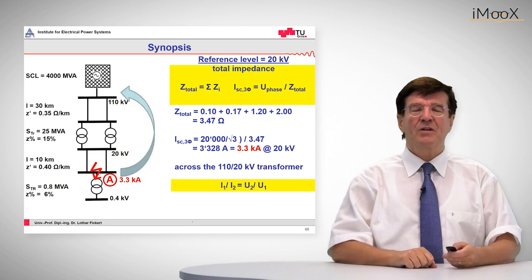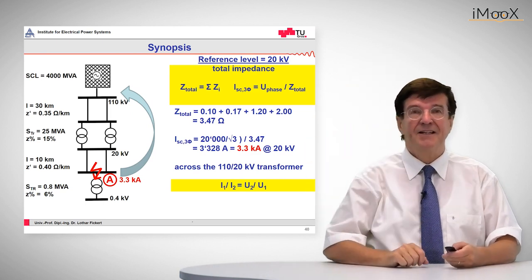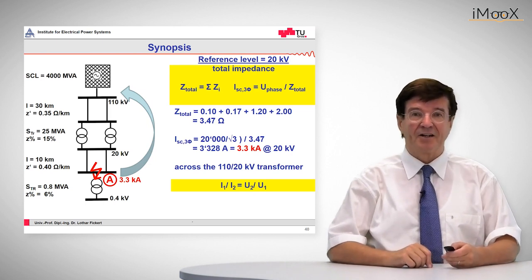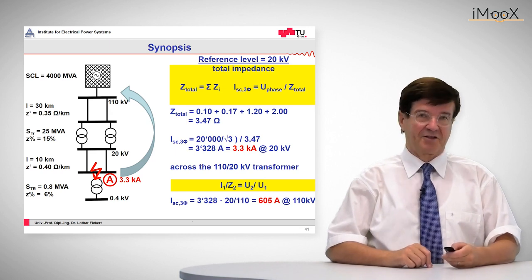Now the question is, what is this current seen from the high voltage side 110 kV? That is given through the transformer by the inverse of the voltage ratio, and the outcome is 605 amps go from the superceding grid into this medium voltage grid fault.